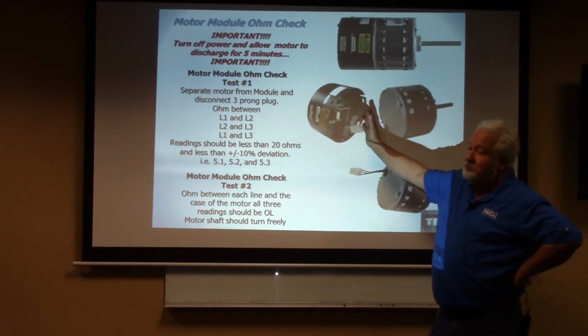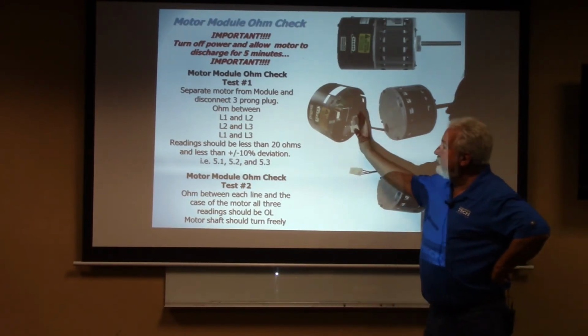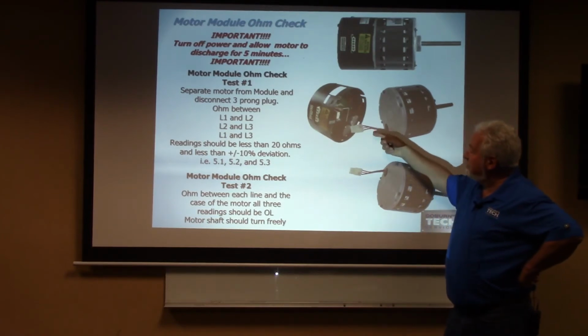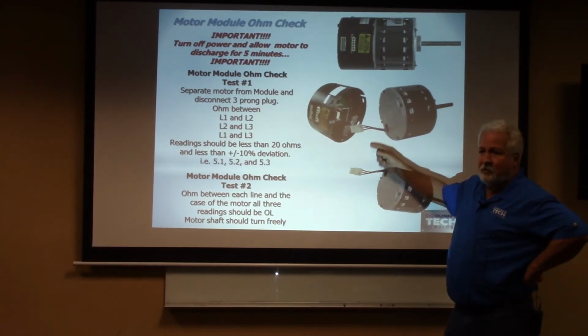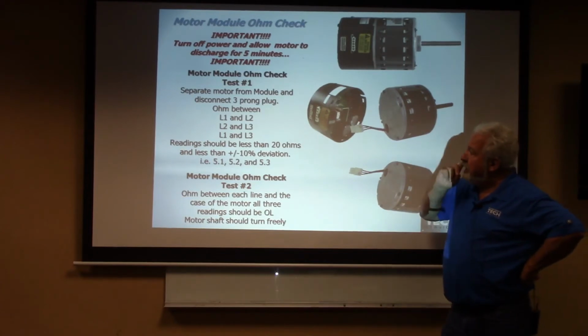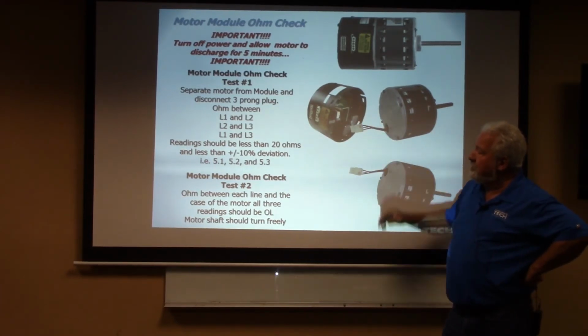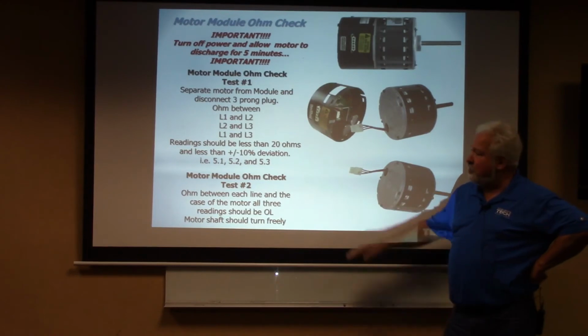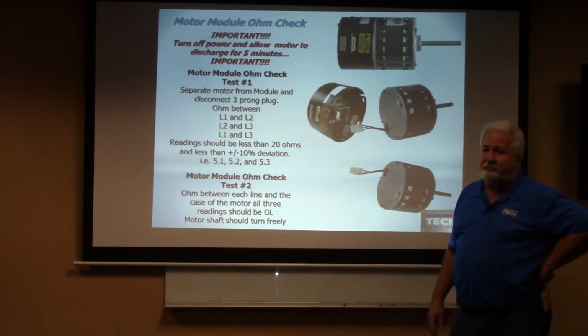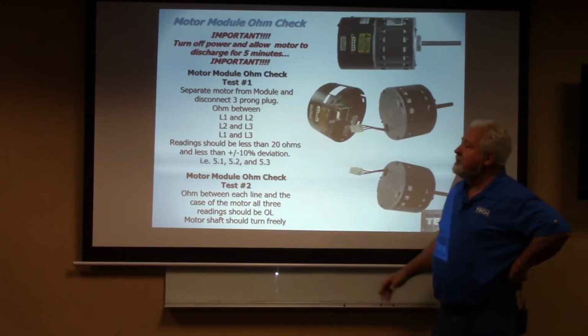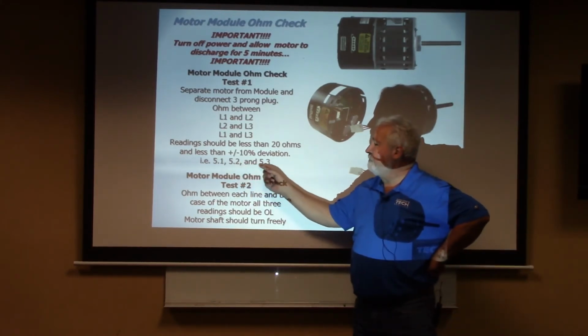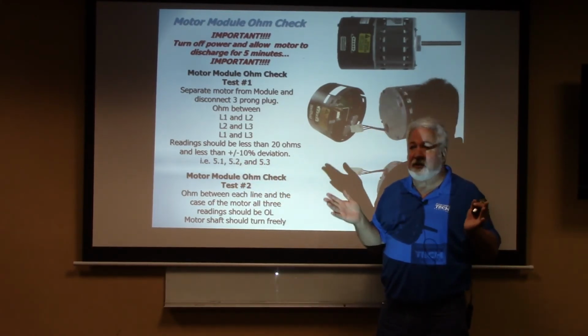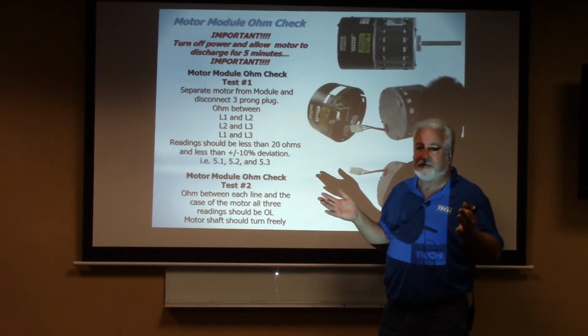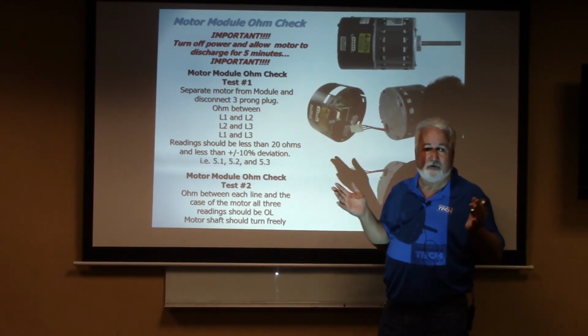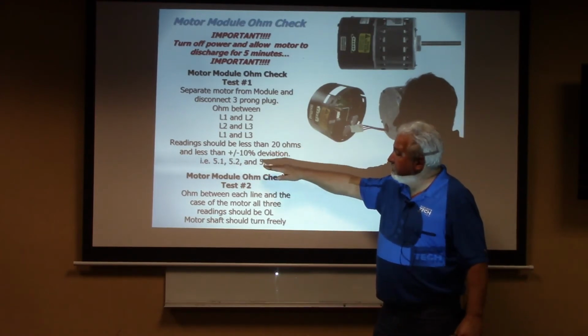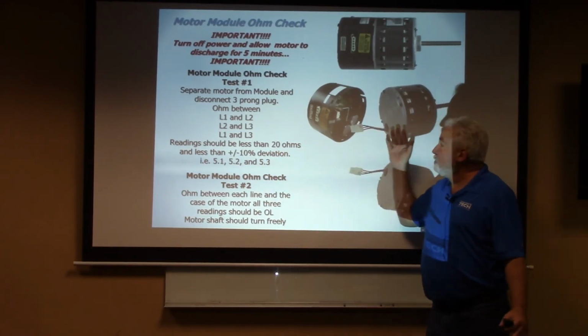Okay, so separate it out, and you're going to ohm, because all we have is 3 wires, right? We're going to just ohm between the 3 of them. L1 to L2, L2 to L3, L1 to L3. The reading should be less than 20 ohms, and should be less than 10% deviation between them. So if I had 5.1, 5.2, and 5.3, everything's good. If I start getting 5.5, that's 10% deviation. Is that right? Good. So in this particular case, 5.1, 5.2, the motor's good.